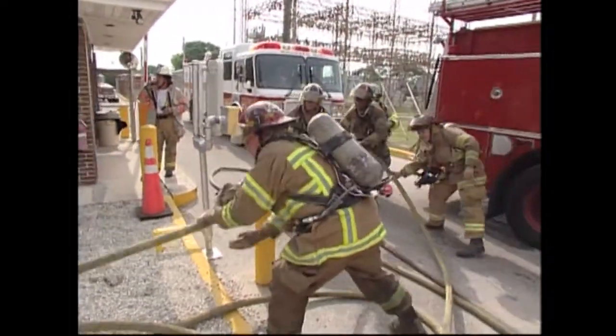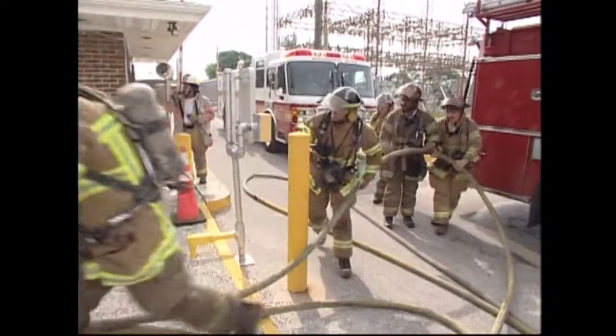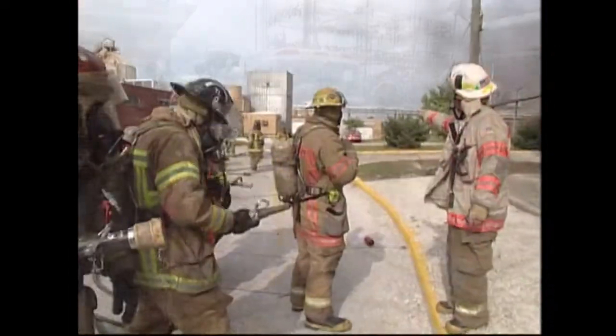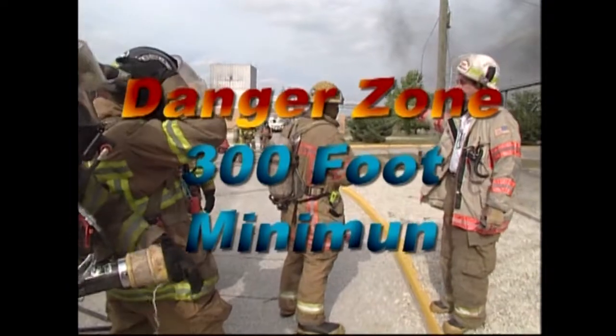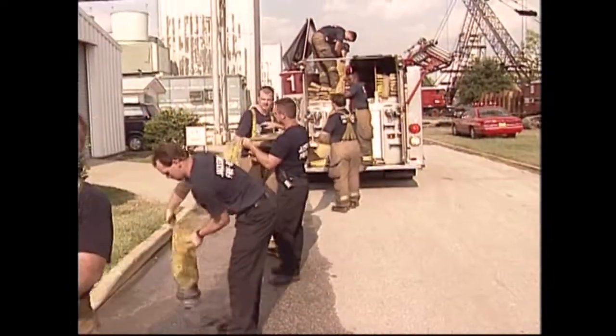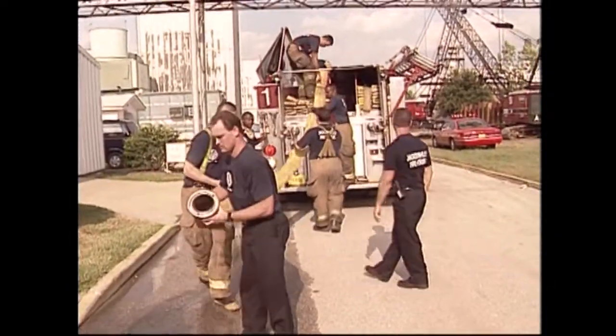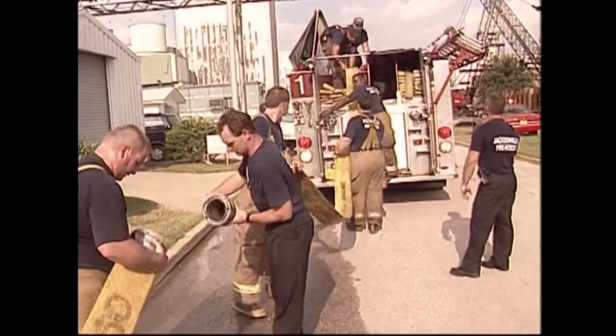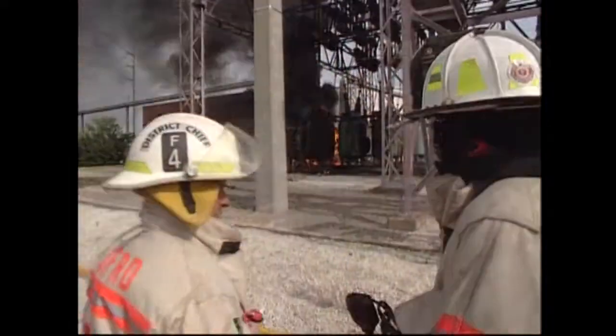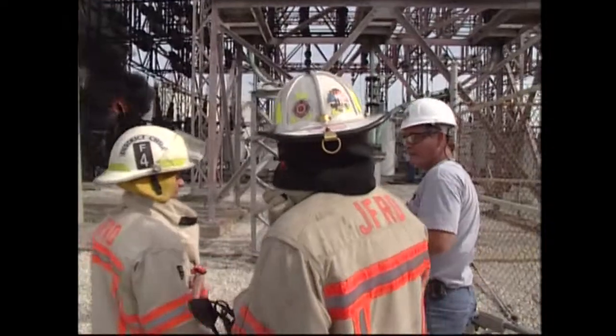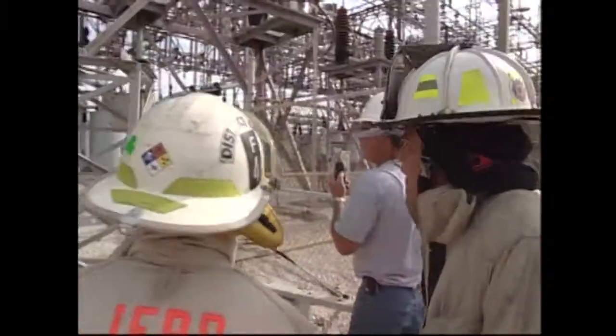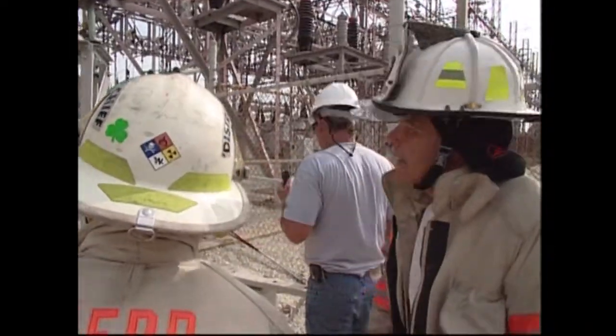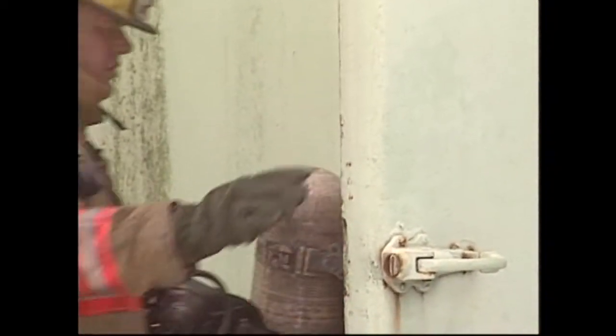Because of the high voltage and possibility of explosion, the danger zone is extended much further, a minimum of 300 feet. Make sure your vehicles are parked at a safe distance and be careful to avoid putting them underneath a power line. When utility company personnel arrive, they'll provide guidance to set up a safe corridor of operations in approaching all the structures and equipment.